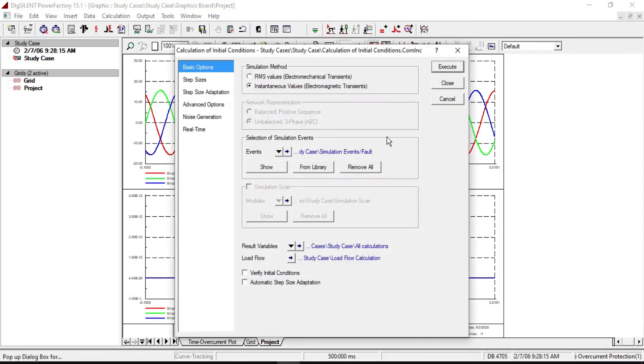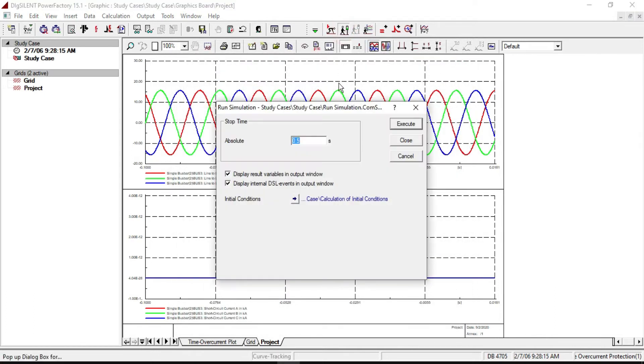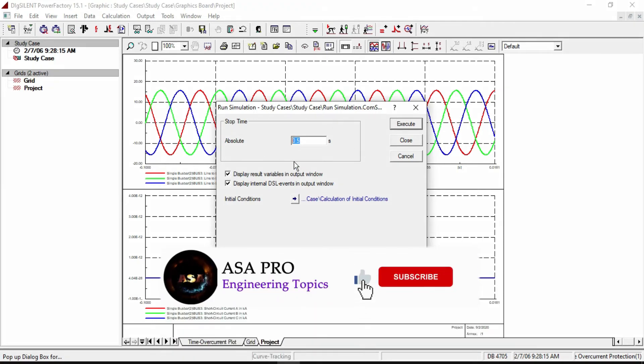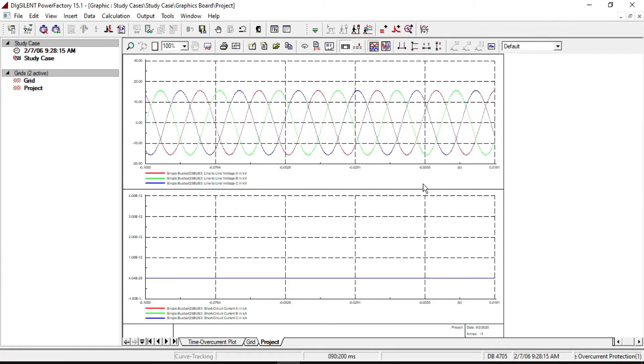First, we need to calculate initial conditions. Then click on Start Simulation. The simulation time should be greater than the time defined for short circuit events. The clearing fault time was 0.3 seconds, therefore the total simulation running time should be greater than 0.3 seconds. Let's set it to 0.5 seconds and execute it.